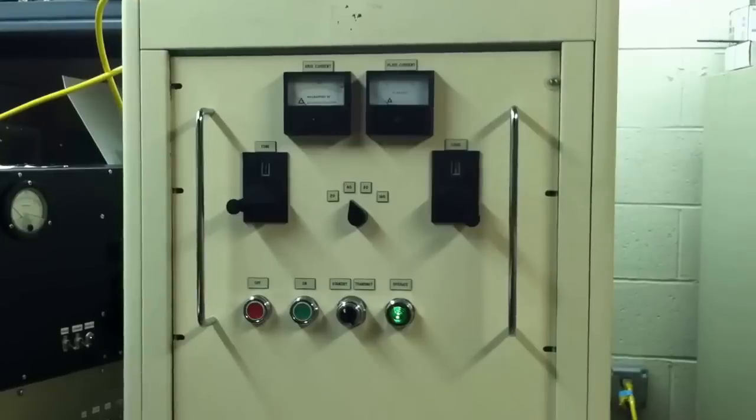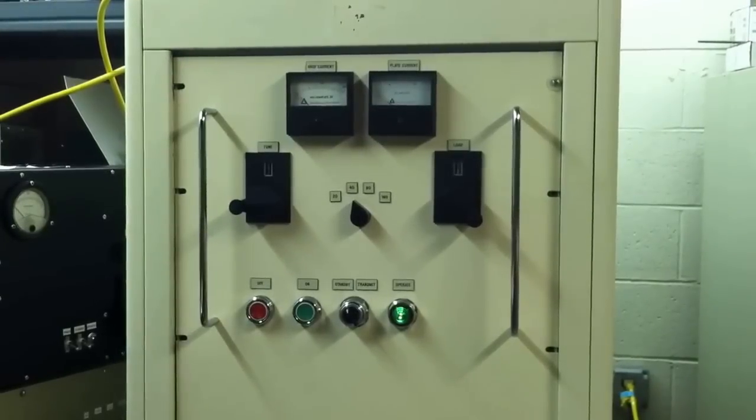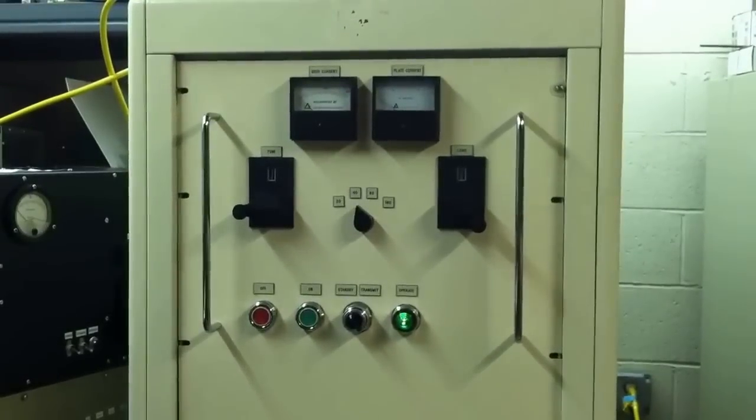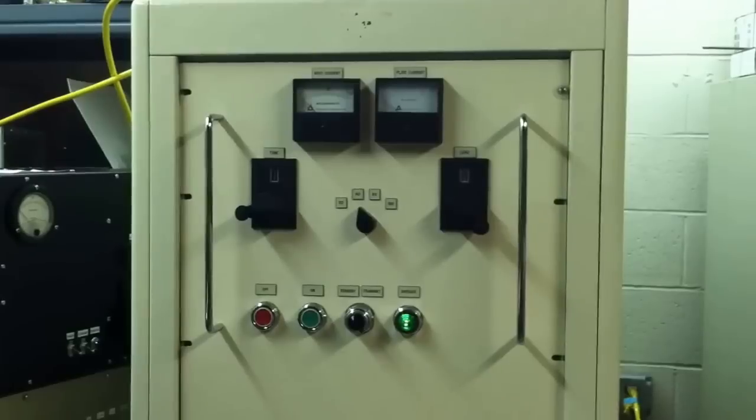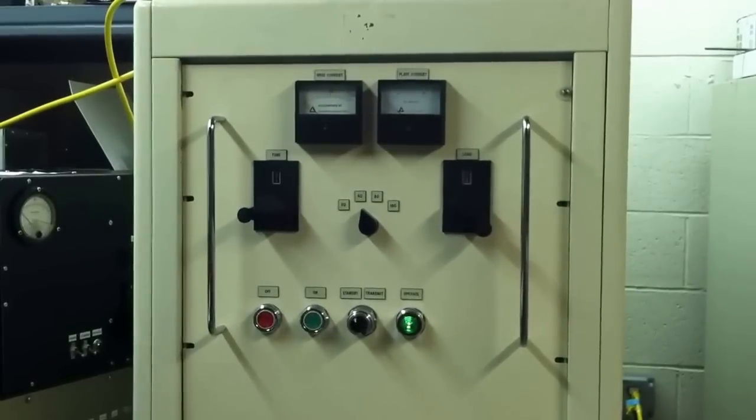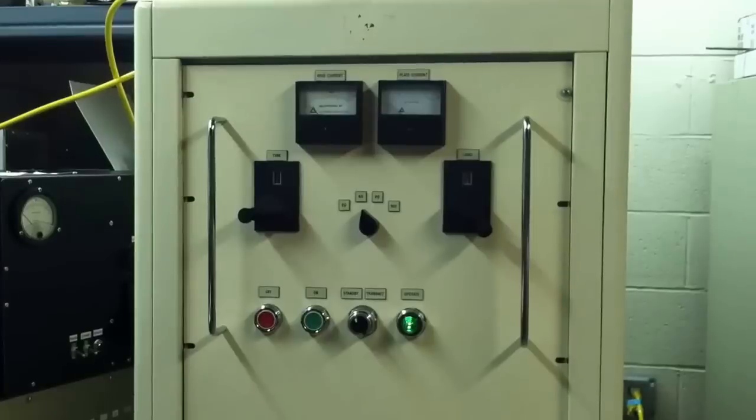Hey guys, just wanted to do a quick update on the 3CPX5000A7. Had a major failure, had an arc over between the anode to the tube and the load cap.